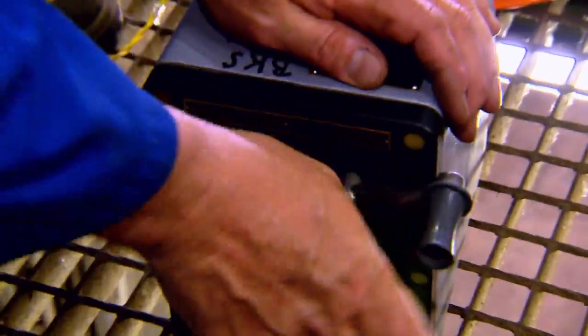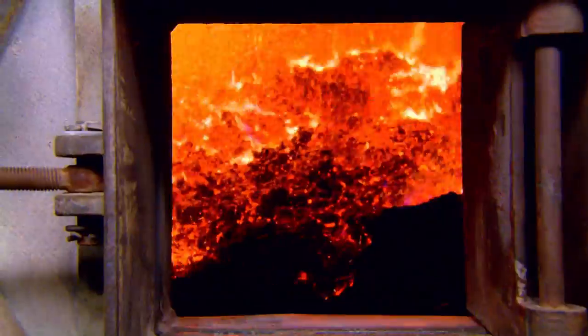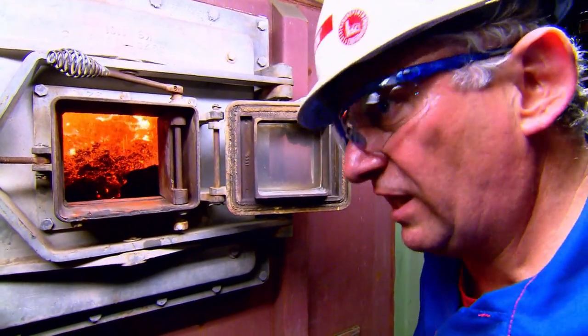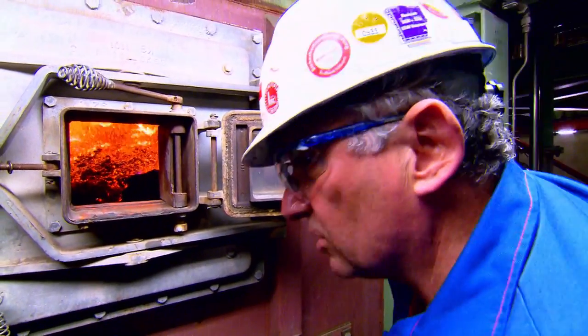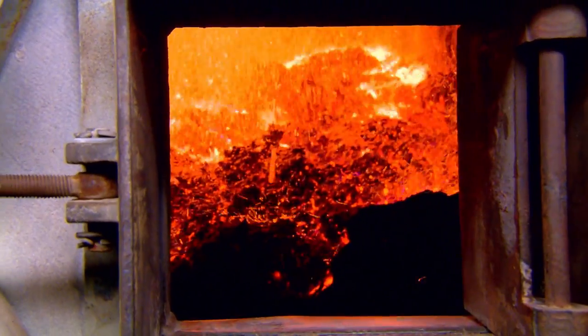The area around the boiler is now secured. Ignition. A huge fireball. But was the blast actually successful? For us, the result is hardly visible — but the boss is satisfied. In a very, very short time, whilst focusing on a high level of personal safety, we've eliminated this slag block and the conveyor can keep running. The boiler doesn't have to be shut down; operations can carry on normally at full capacity. The layer of slag is gone. Operation can continue.